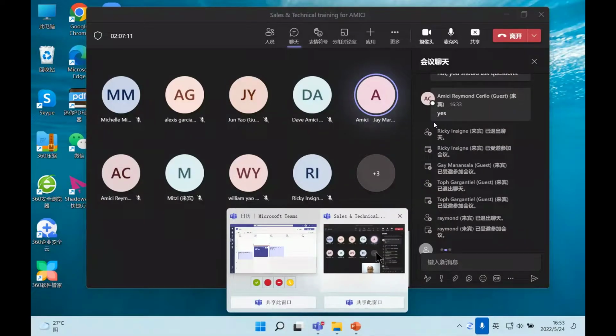About the start mode, how many seconds does it take to change? You mean the speed of the start mode? You mean the display of a restart start code? About 3 minutes. Maybe I didn't catch your point, but this is all very quick. Normally, when it detects the water temperature has dropped 1 degree, it will always make the water pump run 3 minutes first, and then the compressor starts.